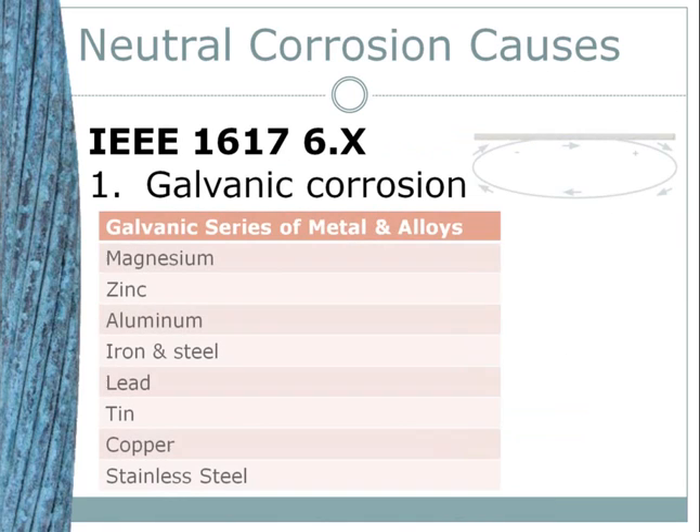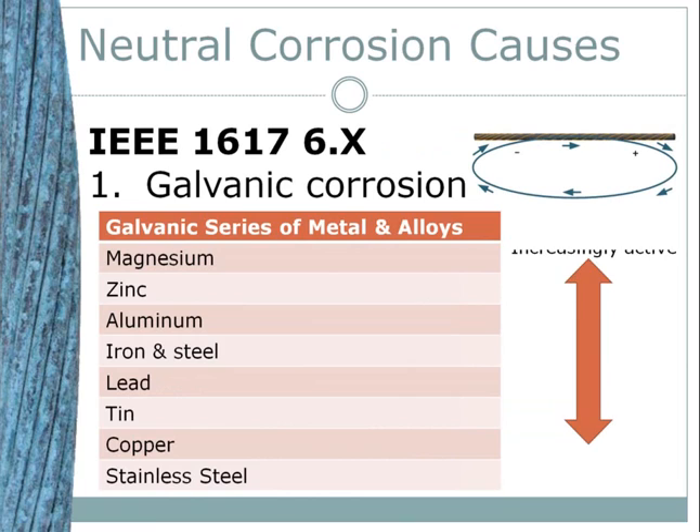There are five causes of neutral corrosion identified in IEEE 1617. The first is galvanic corrosion, which involves the flow of positive ions off the surface of the metal at the anode. These ions typically combine with negative ions in the environment at the anode surface to form an oxide. Corresponding to the loss of positive ions is the release of negative electrons. These electrons flow in the metal toward the cathode region, away from the anode region, where they can combine with positive ions in the environment.